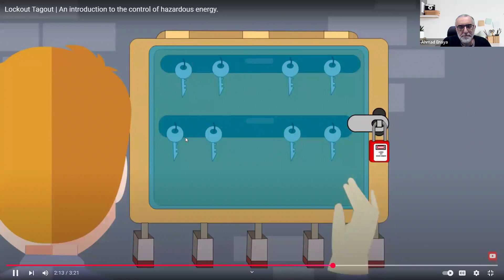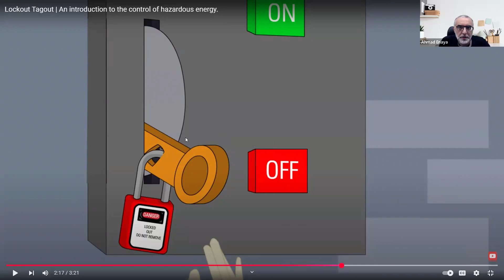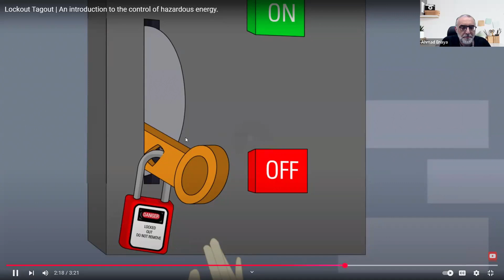And number 4, test the system to make sure energy is isolated. It is important to test because maybe by mistake you did not close it properly - just make sure that this is really shut off and disconnected, and it cannot connect by mistake. The isolation was successful; this is sometimes referred to as tryout.